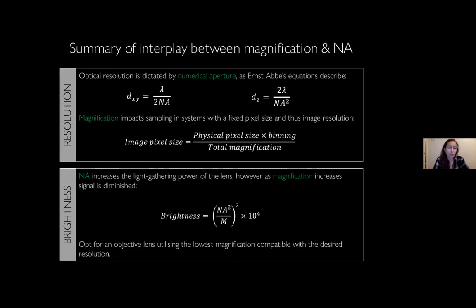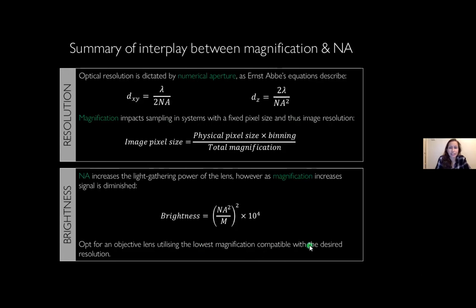Numerical aperture and magnification have a confusing interplay when it comes to resolution and image brightness. In terms of resolution, numerical aperture governs the raw lateral and axial limits — described by Ernst Abbe's equations, the interplay between NA and wavelength dictates the diffraction limit. Magnification, on the other hand, impacts only the effective pixel size when digitizing the image. With regard to image brightness, NA and magnification have opposing effects: NA increases image brightness while magnification reduces it. You therefore want to use the lowest magnification lens possible to still comfortably view the structural detail being resolved.